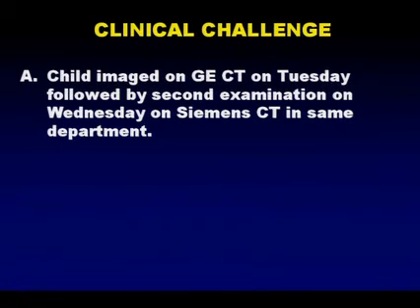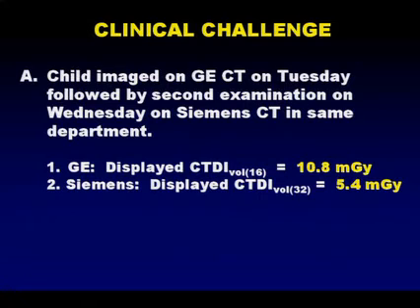So here's a real-life situation. A child was imaged in a department on a GE CT scanner on Tuesday, and there was a need to rescan the patient on Wednesday, and they were imaged on a Siemens scanner in the same department.